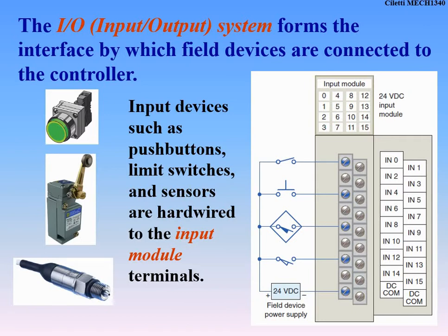I keep saying I/O — inputs and outputs. We call these field devices because they're not at the PLC; they're out in the field. Your PLC and control cabinet don't necessarily sit at the piece of equipment — there might be a designated control center with a bunch of different PLCs, similar to a motor control center. Field devices include limit switches, any sensors, push buttons, pressure sensors, temperature sensors — all those things that are out in the field — and they are wired back to the cabinet housing the PLC.